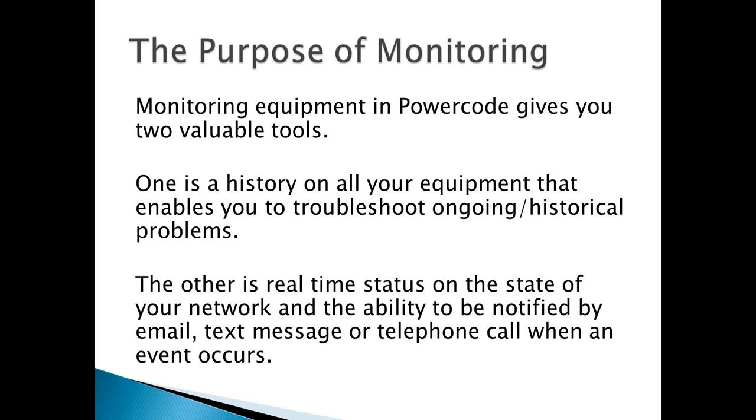The historical probes that we have, quite a few are built in, but this is something that you can modify pretty extensively. So you can build your own probes, you can set your own thresholds for those probes, and we can define what's going to happen when one of those thresholds gets violated. The other thing with the probes is that they're going to keep a history. The real-time stuff is purely real-time, right? What's happened 60 minutes ago or even 60 seconds ago is not necessarily going to be visible. The probes are all going to automate the historical gathering of data.